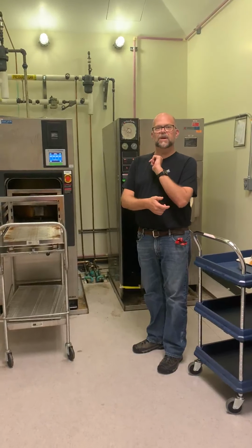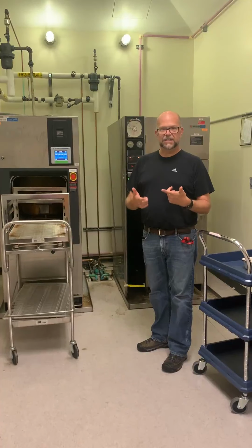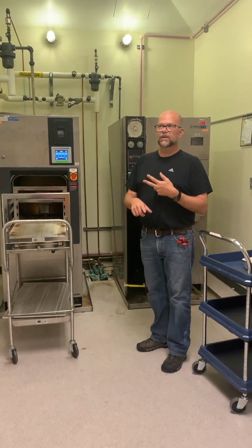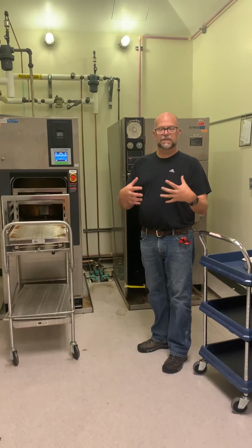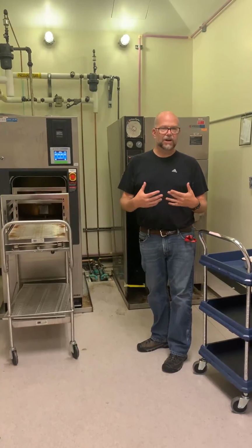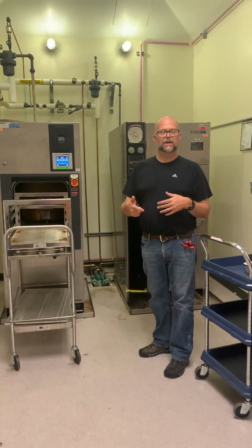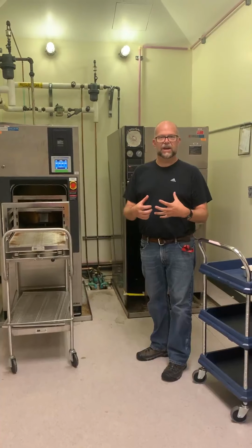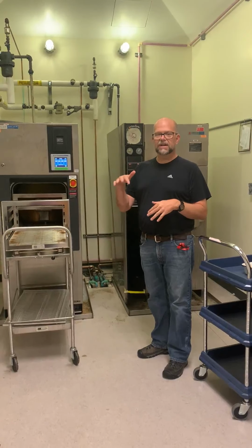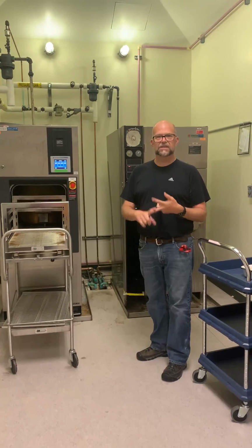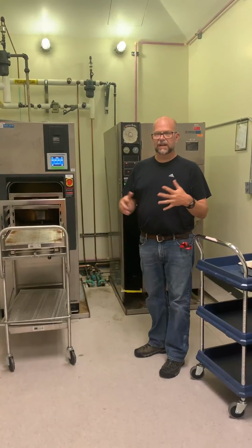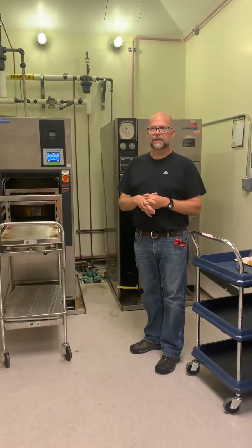autoclave gloves preferably that go up to your elbow. And eye protection is an option, but it's recommended. You also want to bring in the material that you're autoclaving on a cart. Don't transport anything in or out of this room by carrying it. It increases the risk of you dropping something that's superheated and creating a huge mess and a possibility for injury.